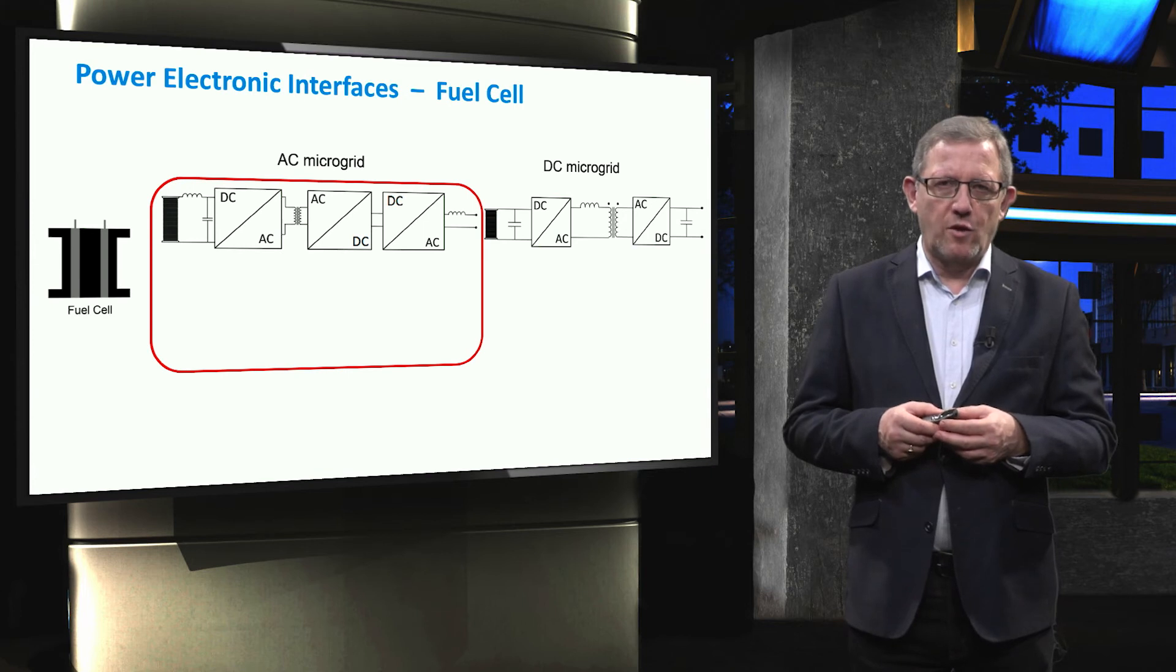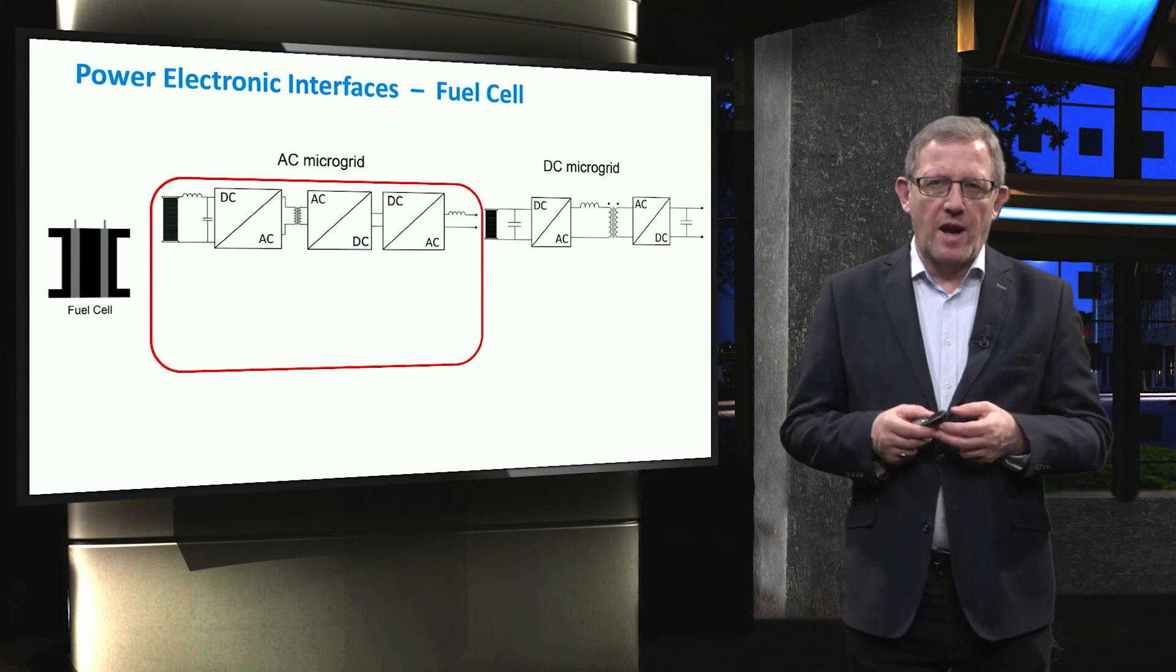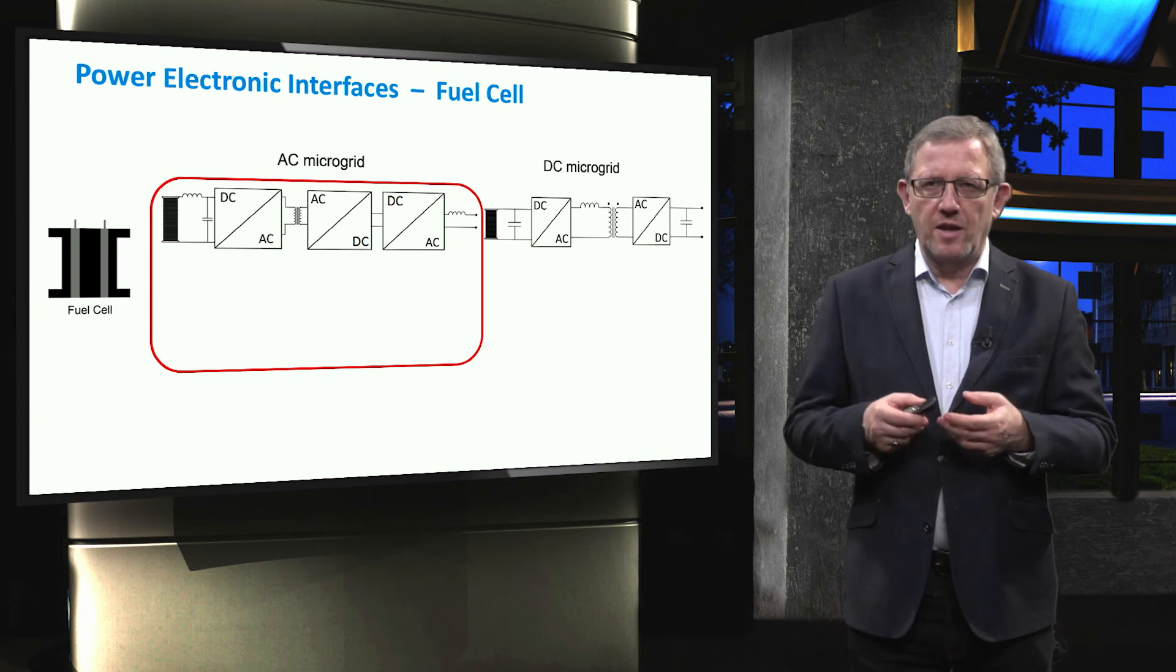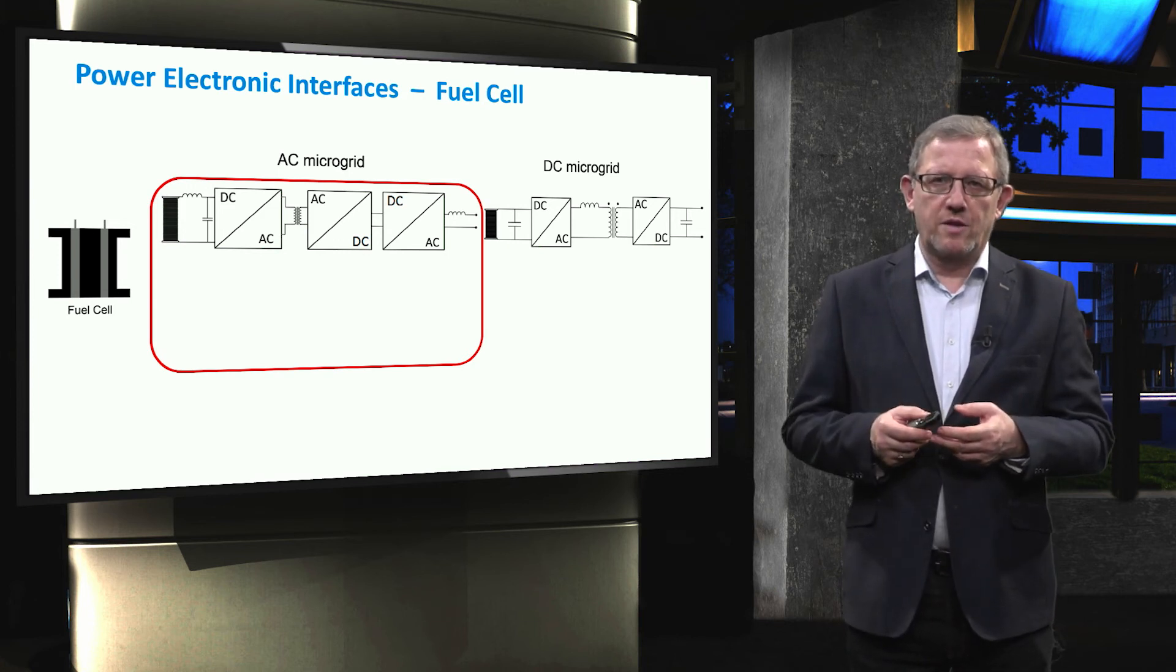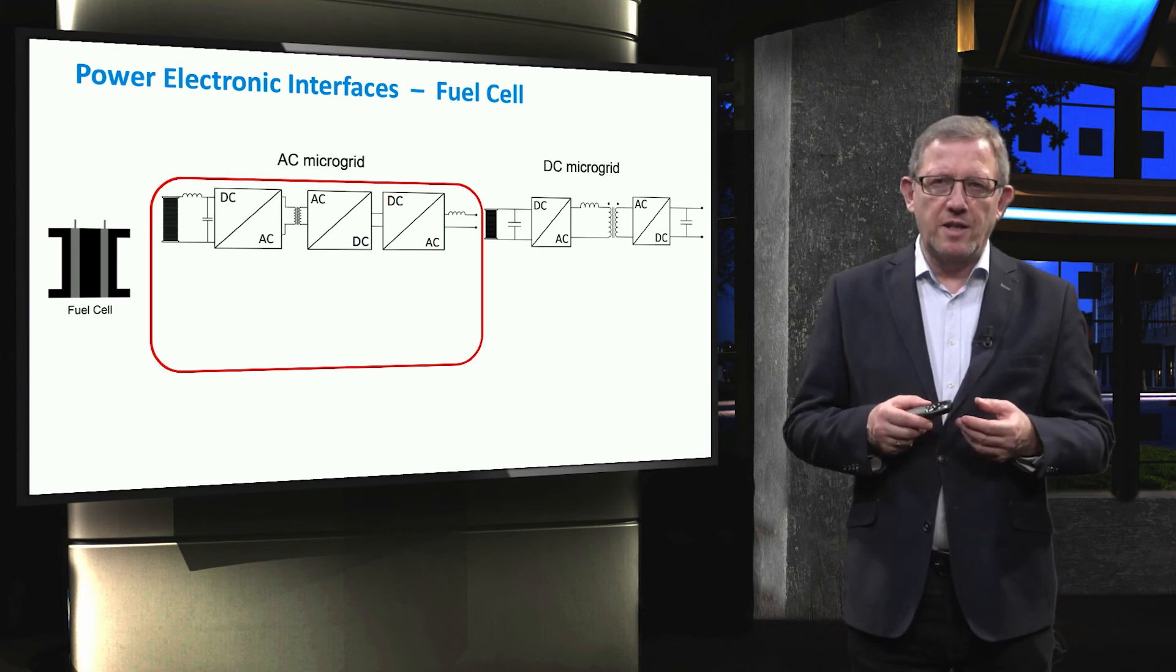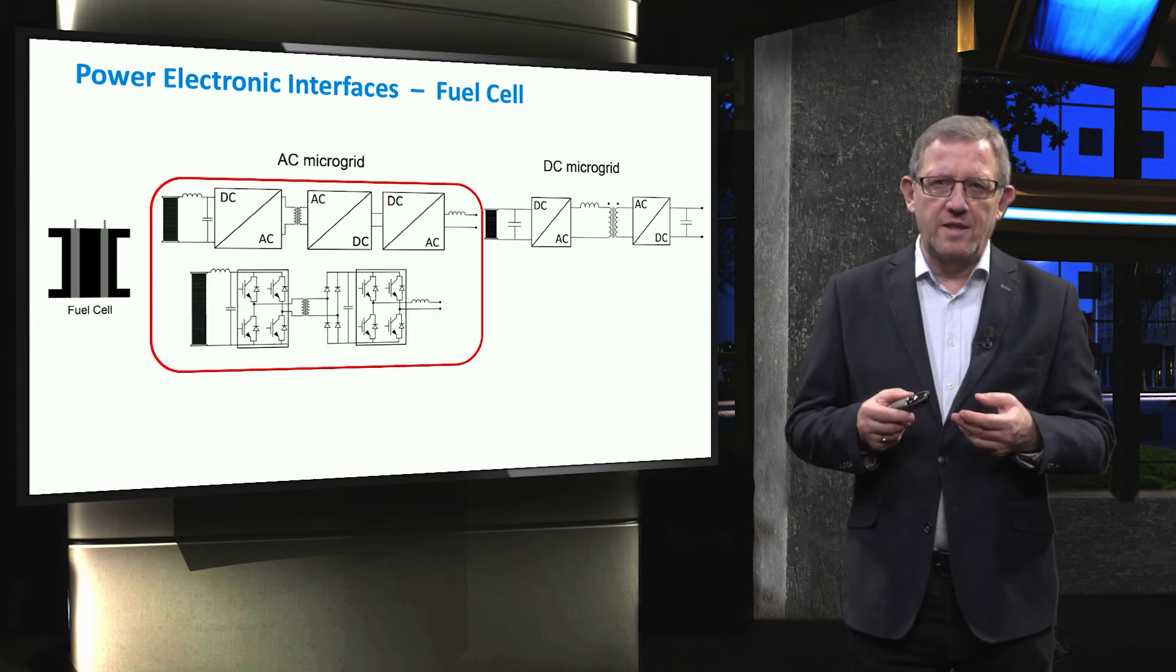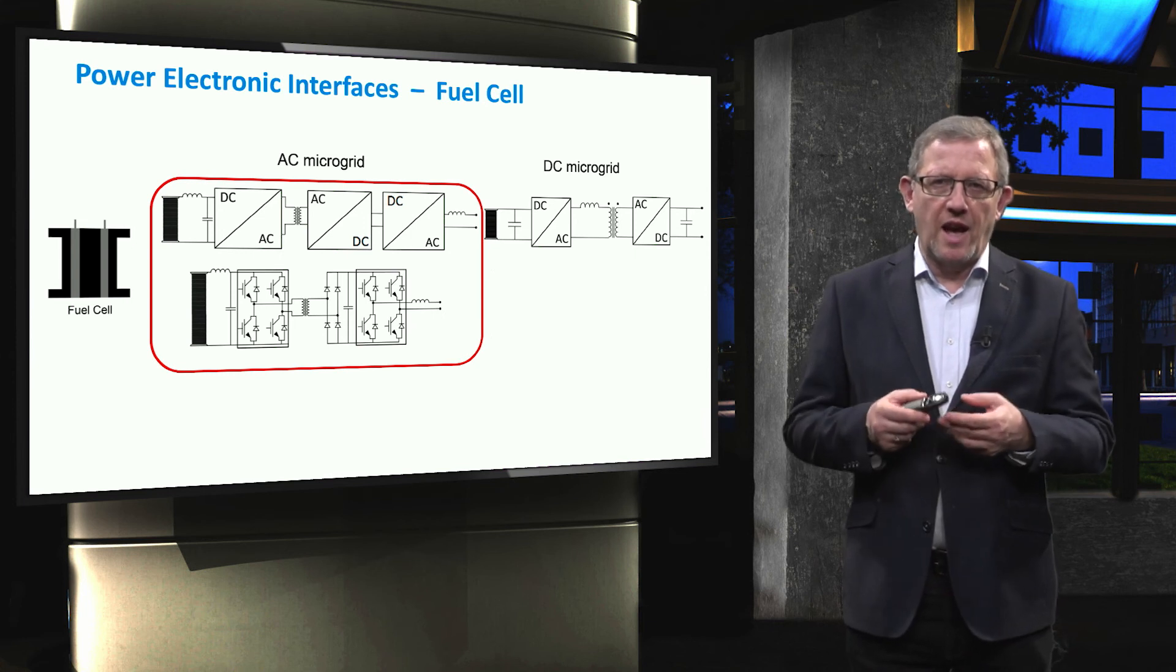The last storage technology for which we introduce the power electronic interfaces is a fuel cell. To connect a fuel cell to AC microgrid, in the simplest form a DC to AC converter can be used. However, to efficiently achieve higher voltage levels, it is possible to increase the number of conversion stages and install a high frequency transformer between the two-leg DC to AC inverter and the diode bridge.